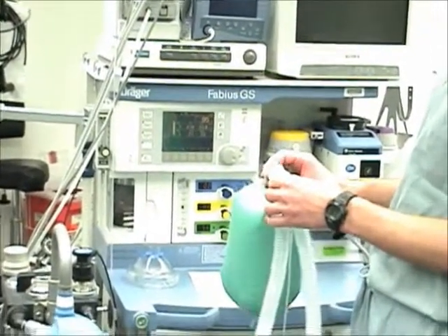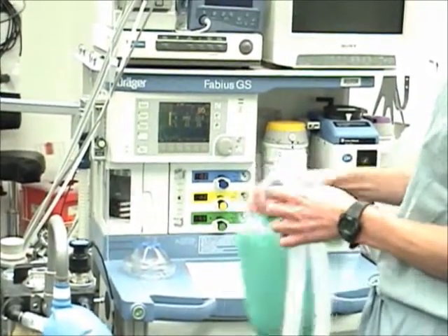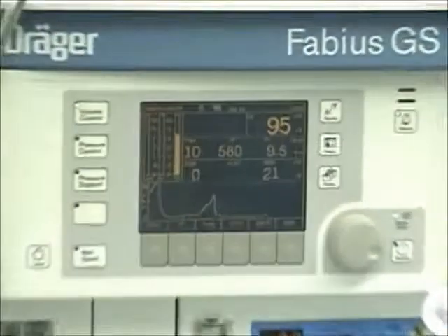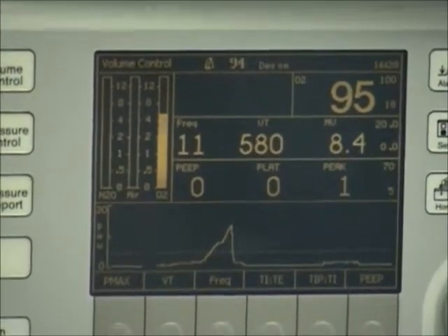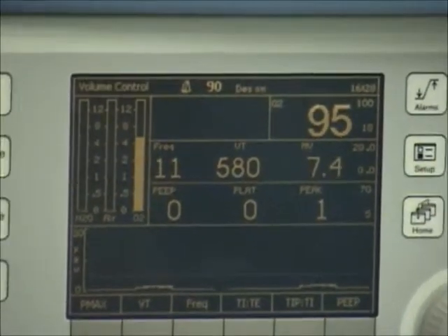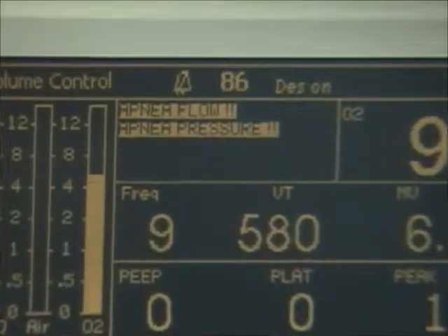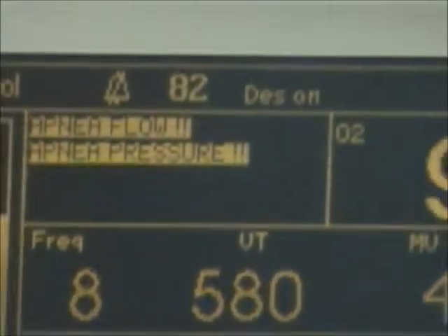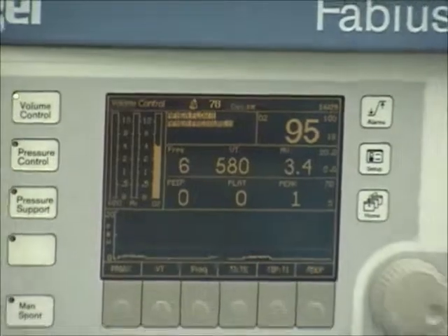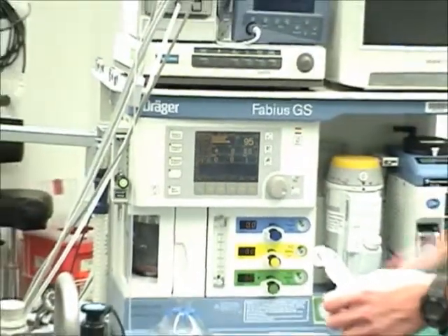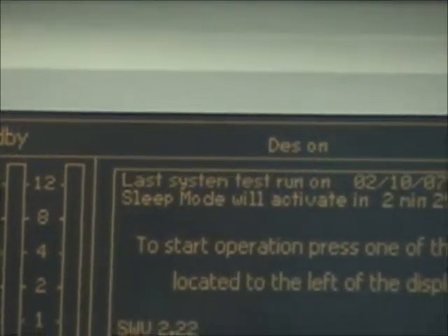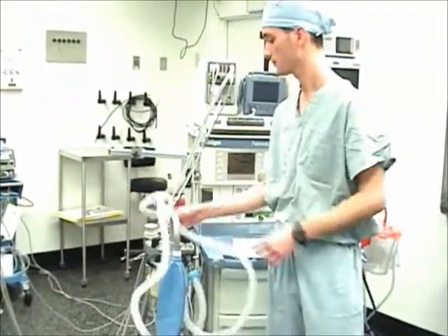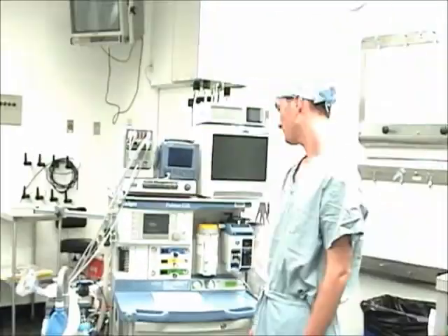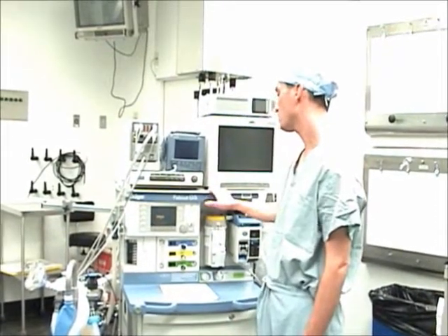Remove the artificial lung from the Y piece and assess the presence of an apnea flow and apnea pressure alarm. Apnea flow, apnea pressure. Turn oxygen metering valve to 0. No fresh gas. Press the standby soft key and confirm the selection with the rotary knob. Reconnect the face mask to the circuit Y piece and fully open the APL valve. That completes the daily checkout procedure for the Fabius GS. The machine is ready for use for the first case.